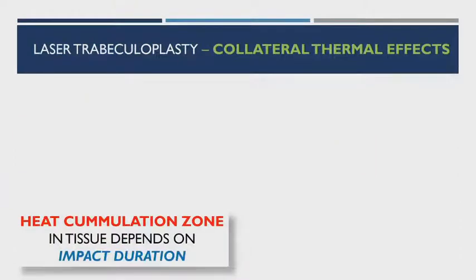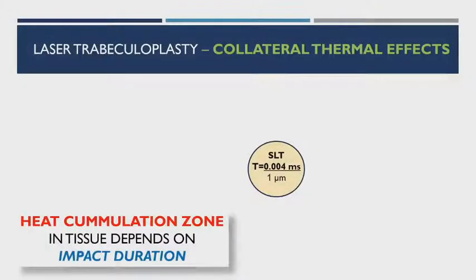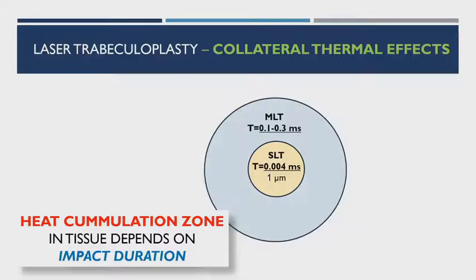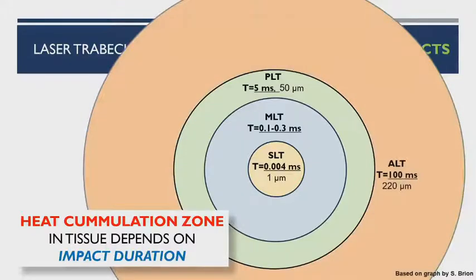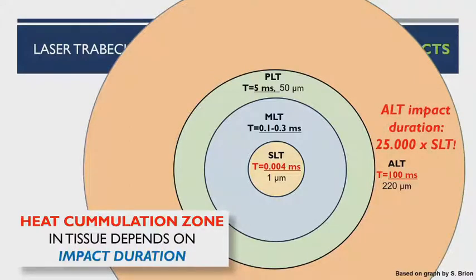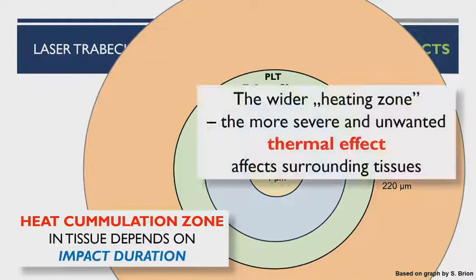Besides spot size, energy, and repeatability, a very important issue is impact duration. Impact duration is directly responsible for the heat accumulation zone around the laser impact as energy spreads to tissue. In SLT, the heat accumulation zone is very small — only one micrometer — because the impact duration is really short: 0.004 milliseconds. It's bigger in MLT, even bigger in PLT at 50 micrometers. In ALT, the collateral thermal effect is huge and covers all the trabecular meshwork, because ALT's impact duration is 25,000 times longer than SLT's. The wider the heating zone, the more severe and unwanted thermal effects on surrounding tissue.